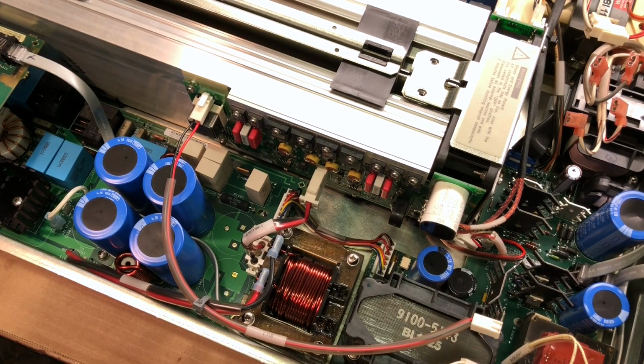The reassembly is almost complete on the 6812B, so I'll be able to power it up soon, and we'll see if it functions. However, the next thing that I need to do is to reconfigure the AC input voltage range. It is currently set for the higher 220 to 240 volt range, and I want it to be set for 120 volts. So there's 3 areas of concern when you're changing the voltage range on this instrument.